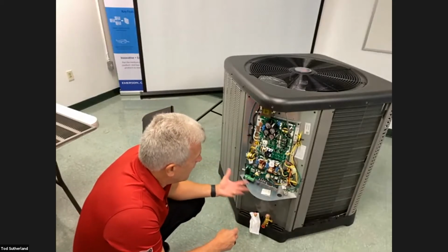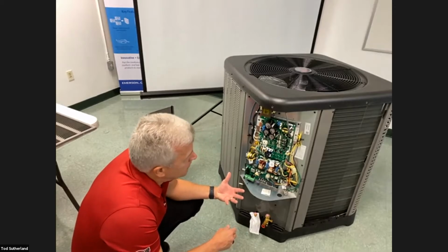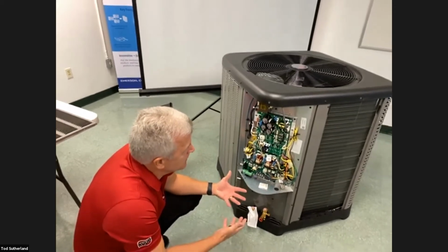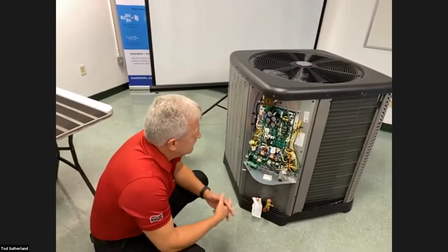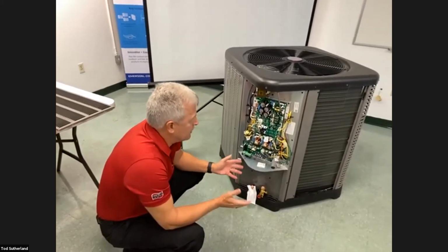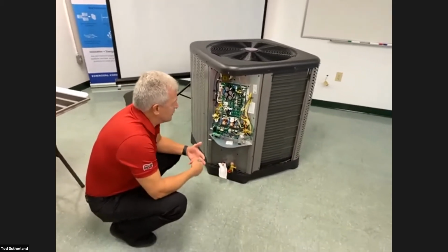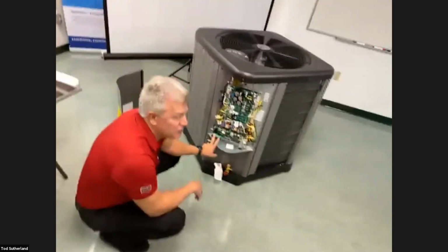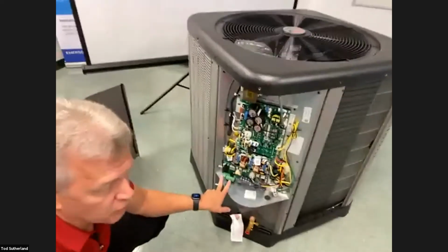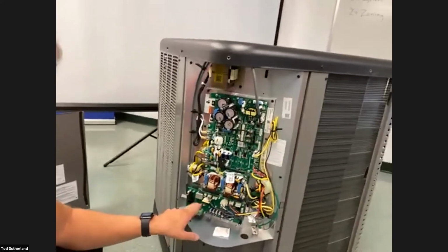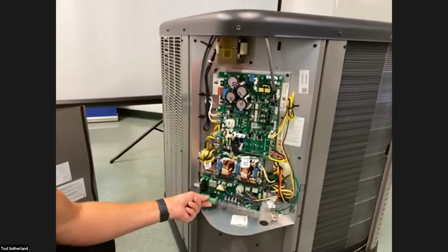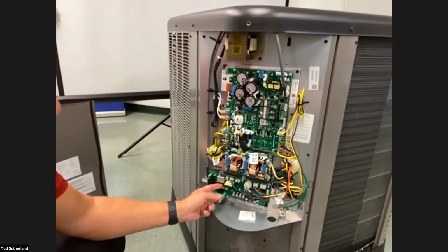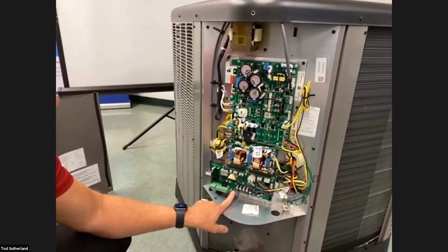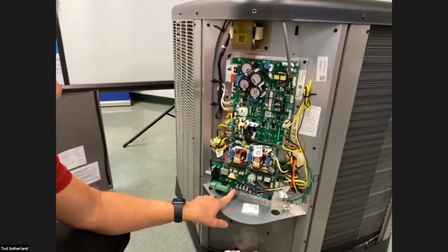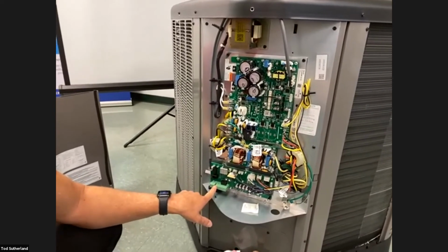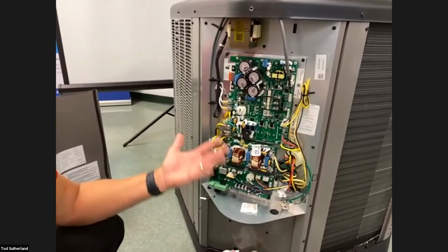As you're wiring the high voltage on this, as far as diagnosing the system, it's really not much to it. You're going to have your low voltage coming into here, so you want to make sure you've got 24 volts here, obviously. You should have lights blinking on the board. If you've got 24 volts coming into here and you don't have any of these lights blinking on the board, check your fuse, okay? If you've checked your fuse and your fuse is good and you've got 24 volts coming into here and you've got no lights, you have a bad board, okay?